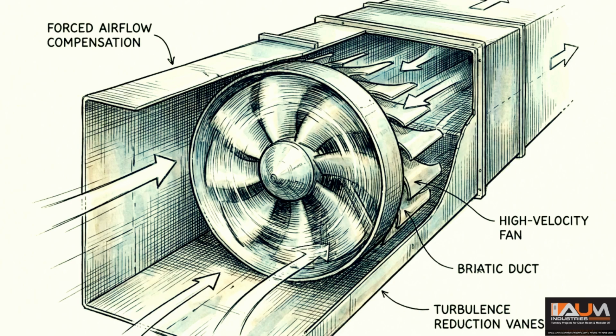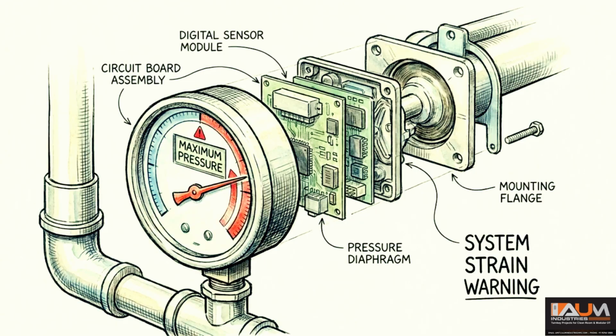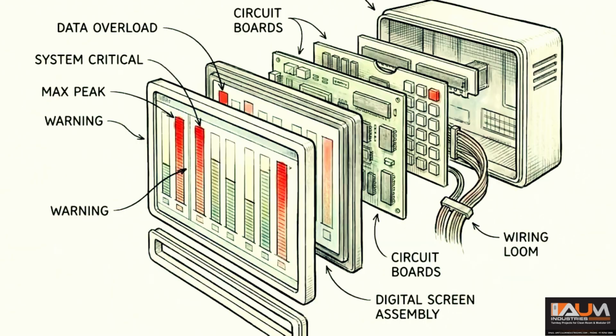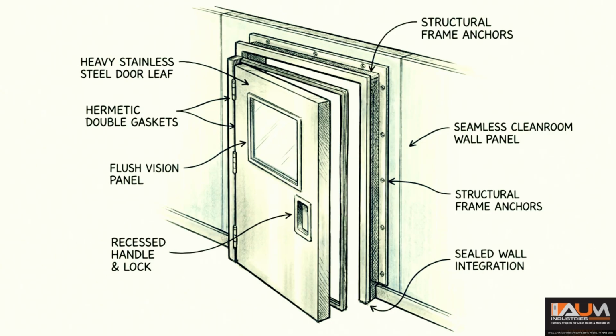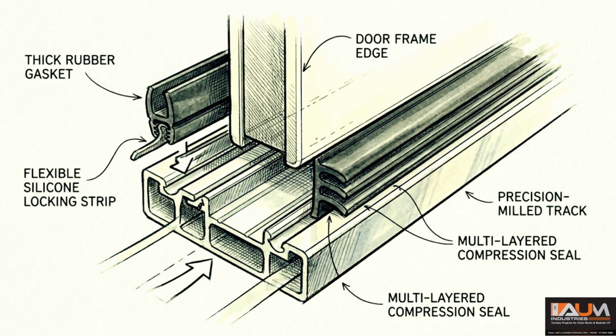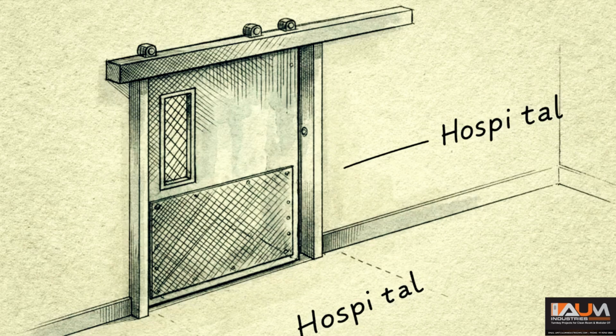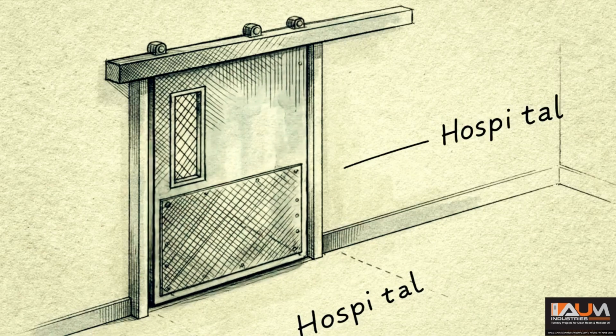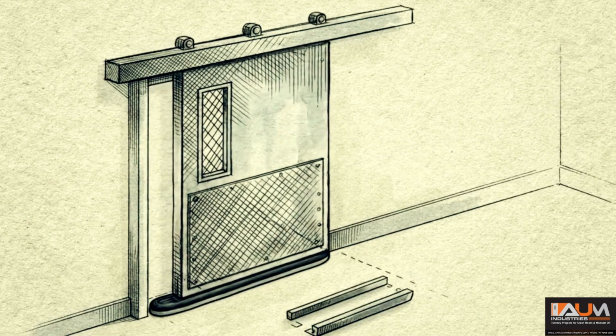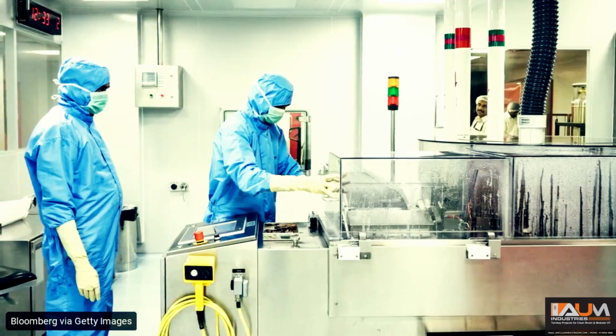To make up for that tiny, continuous leak at the floor, the multi-million-dollar HVAC system has to work harder to maintain the room's pressure. Eventually, the system overcompensates, leading to massive airflow balancing failures. Fixing this requires a specialized healthcare-grade hermetic door, a barrier engineered to physically lock into the cleanroom walls and permanently seal the gap. The most sophisticated air filtration system in the world cannot maintain sterile conditions if the perimeter allows air to bleed out of the room. Air pressure is only half the battle.